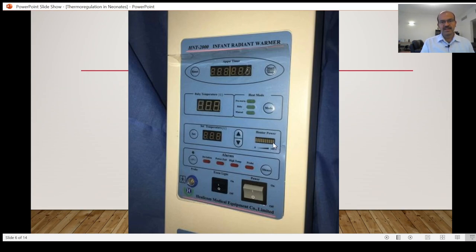If you look at the panel on most radiant warmer systems, you have an indicator of the extent to which the heater output is used — from 10 percent to 100 percent heater output. If there are no lights on, there is no heater output. If you have five marks, that means 50 percent of the heater output is on.